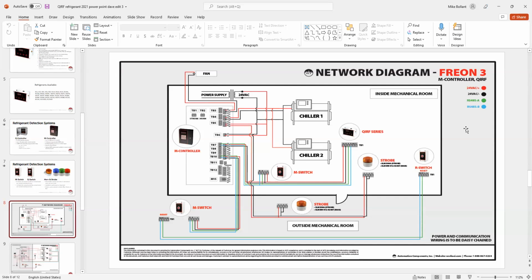Now the M controller, I've seen it in different places. You can mount it inside the room or outside the room. That will display what's going on in the Freon sensor, so you don't have to get down on your knees at 12 inches off the floor and look at that. Every code is a little bit different, whether it's mounted inside or outside, so that's usually on a local basis, whatever the code says.